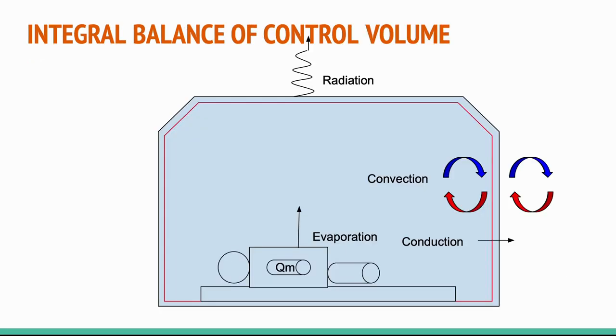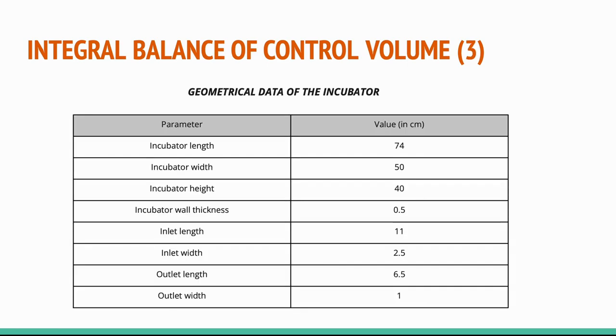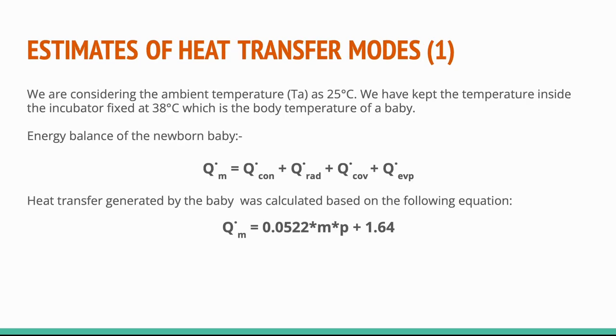Here we have tried to show the heat transfer in an incubator. We can see that evaporation is happening from the baby's body, conduction and radiation are taking place through the system walls, and convection is happening with the airflow inside. We have assumed a fiberglass wall incubator for our calculations, and the physiological data of the baby is as shown. The incubator has been assumed to be approximately a cuboid with dimensions 74 x 50 x 40 cm.